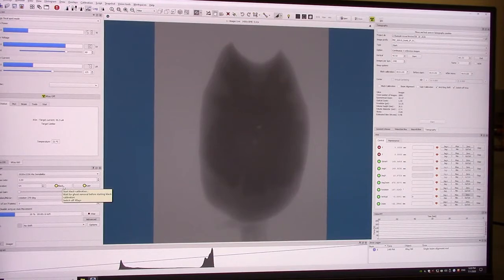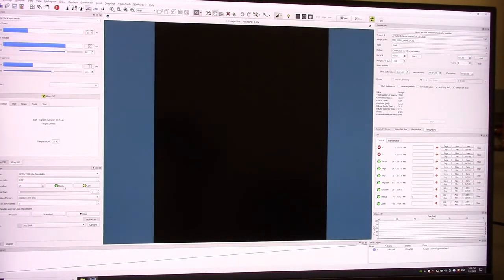If you were to do black calibration, you just click on the black calibration button, and the system will switch off the X-rays and wait for the ghost image to be removed. Okay, so for the black calibration, after the X-ray has been shut off for roughly 5 minutes or so to get rid of the ghost image, basically you just hit the black calibration button. It starts the black calibration. It only takes, I don't know, maybe 30 seconds or so, and it'll be done. Okay, the black calibration is now finished.